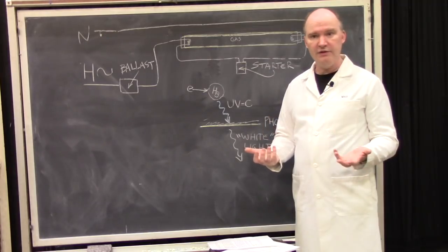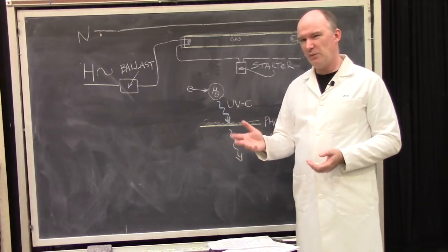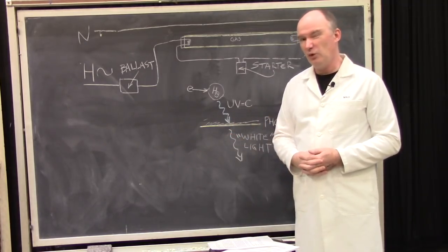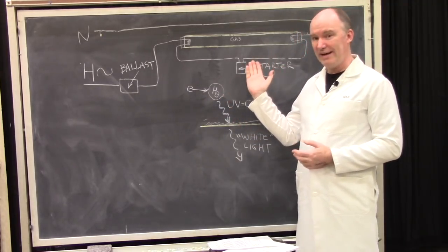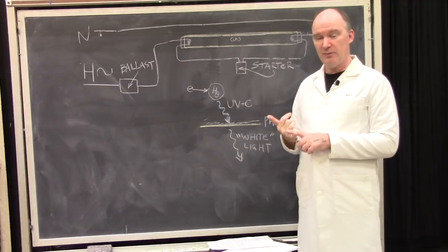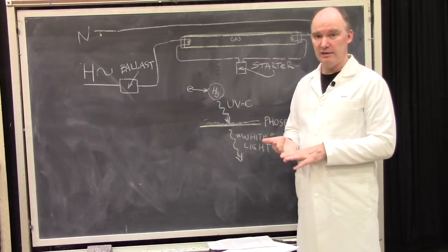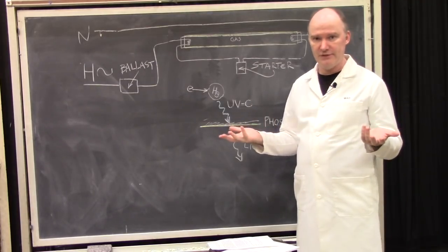Depending on the quality of your ballast, at some point, they will just snap out. At below a certain level, they just can't maintain that arc no matter how fancy their circuitry is. On a good ballast, this may be five percent. On the cheaper ones, it may be snapping out at around twenty percent. Also, if you want a color other than white-ish, you need to either have a special phosphor coating or put a gel in front of it, which introduces the same losses we discussed earlier.